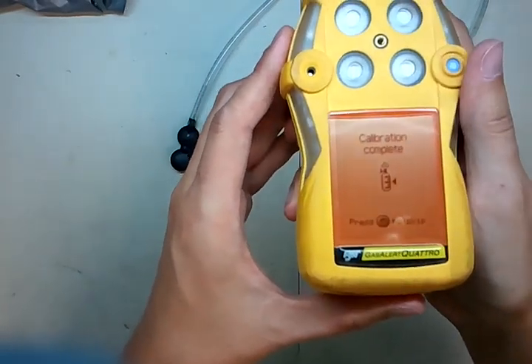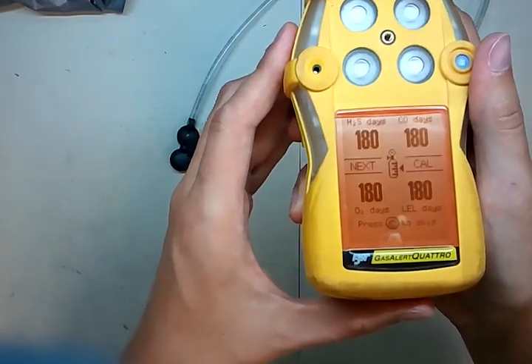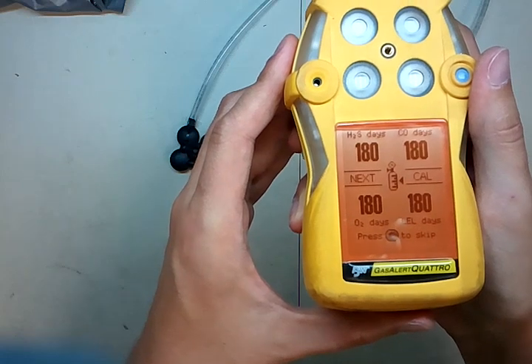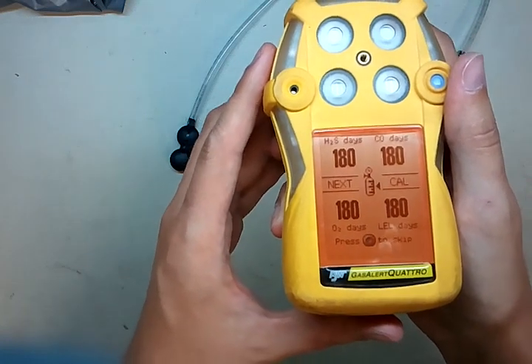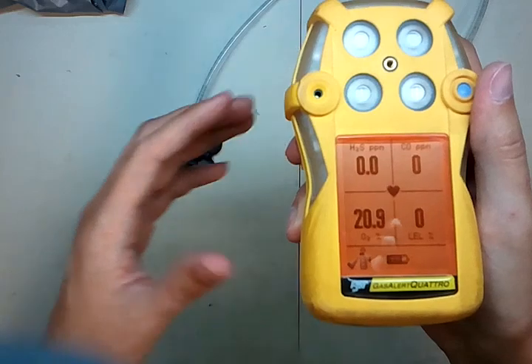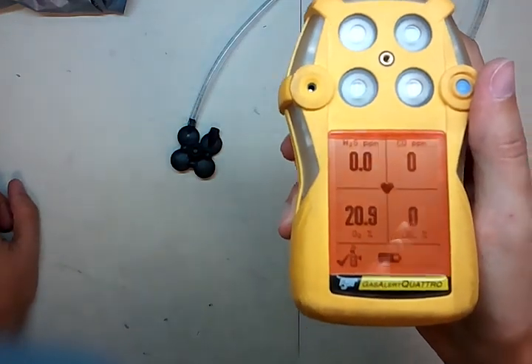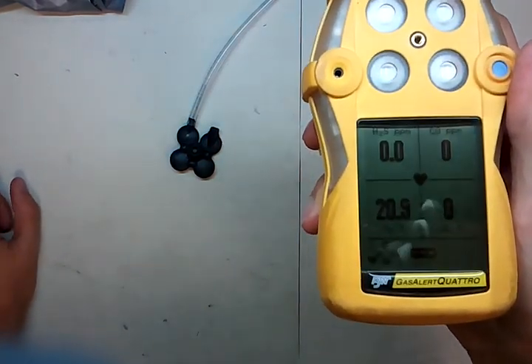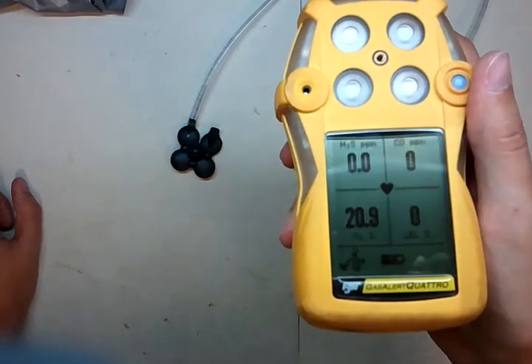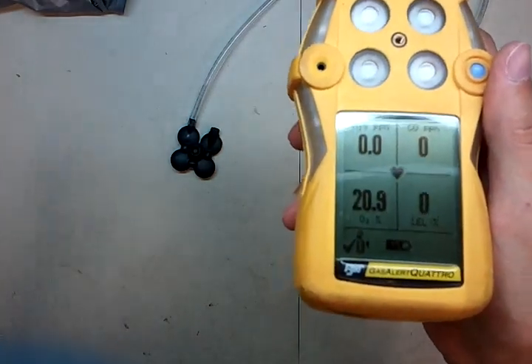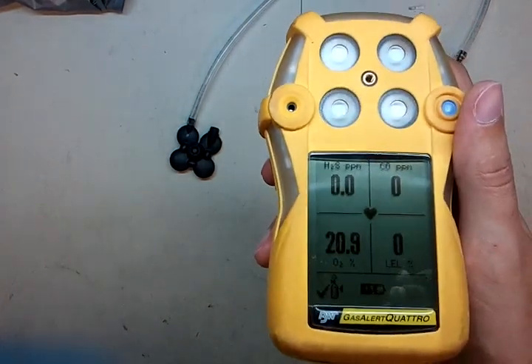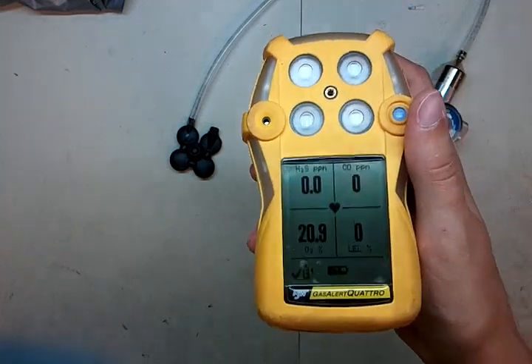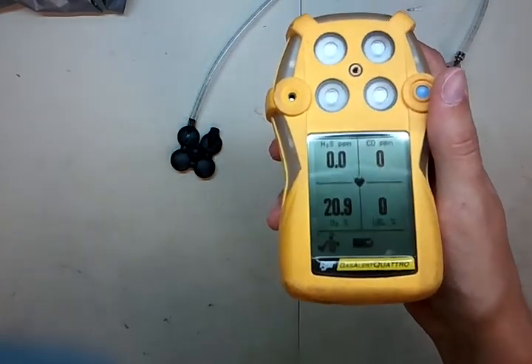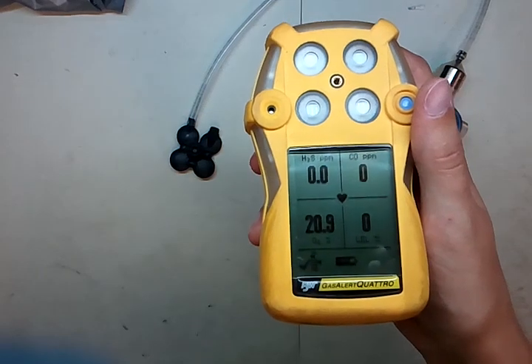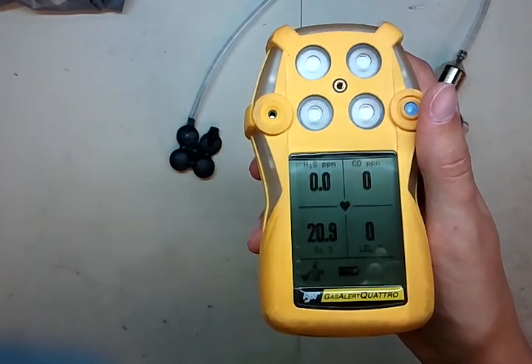You can press this button if you want to skip forward, but even if you don't, it'll come up with a normal screen and tell you, hey, you have 180 days till next cal. Now, I don't agree with that. I honestly think you should be bumping the monitor before each use and calibrating it about monthly, just to keep yourself safe. If you try and run a procedure where you say, hey, we're only going to cal every 180 days, things tend to get out of control pretty quick. So I always say bump daily, cal monthly, and if you ever have an issue like an exposure, you should probably recal the instrument. Okay?